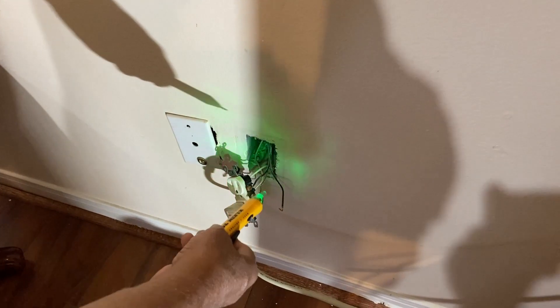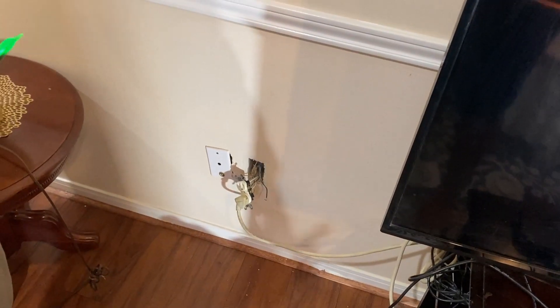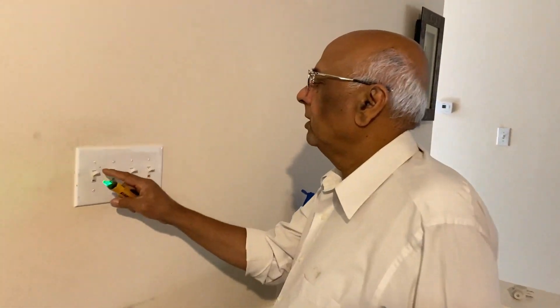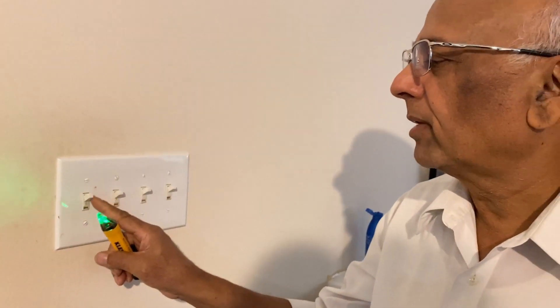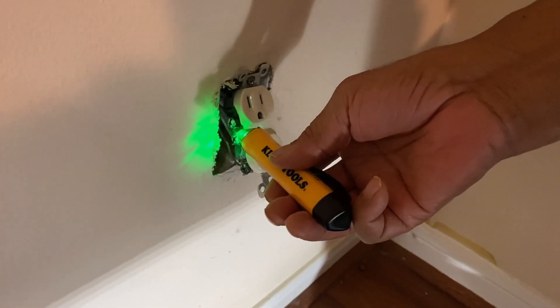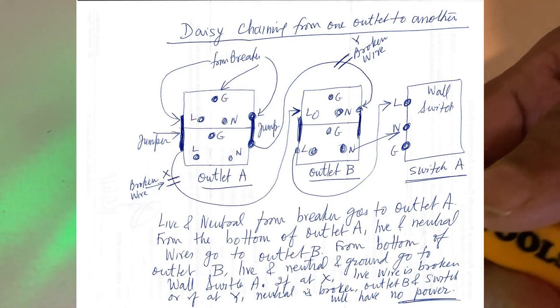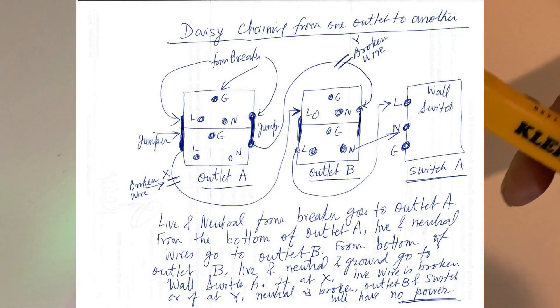What I found is I opened this one and found that this wire here was disconnected — it was loose. So I disconnected it. The power comes here, and then this goes to the switches. The power from here — this switch sends power to the light, this switch sends power to that light, this switch sends power to that light. And then the power also comes here. But here you will see that there is only one wire. Normally you have two wires, one coming in on the top and one going out on the bottom, but here there is only one wire. That means no power is going out to another receptacle.